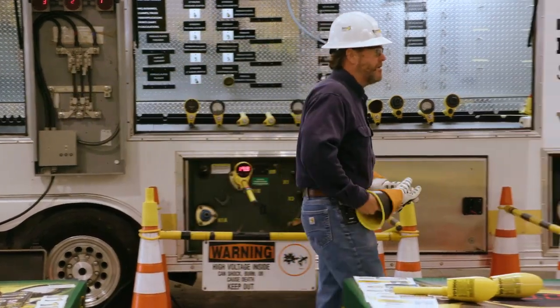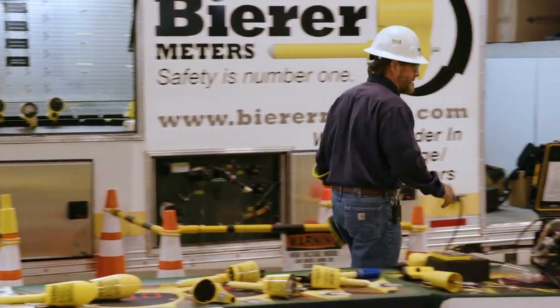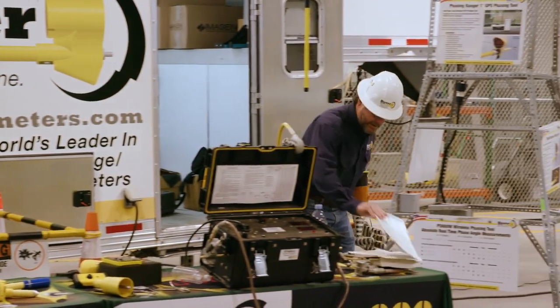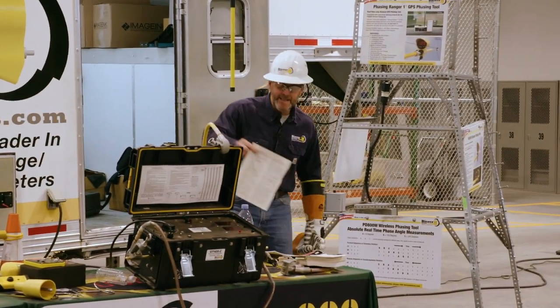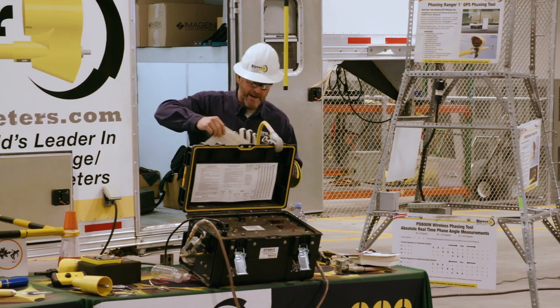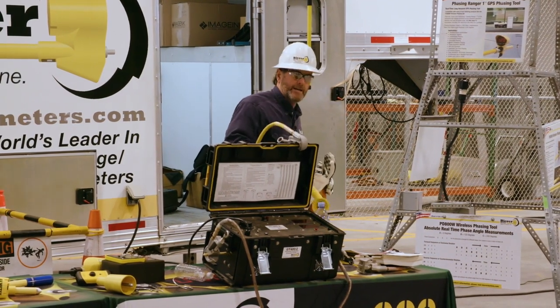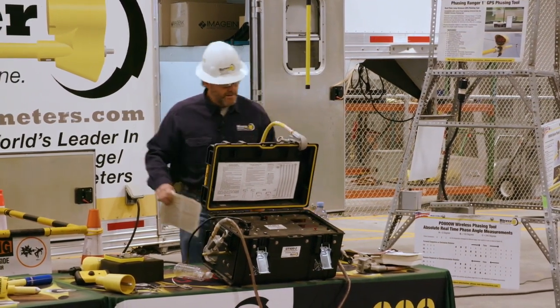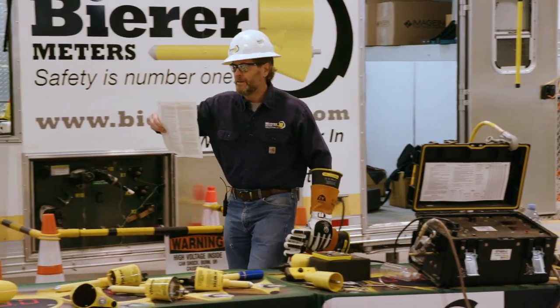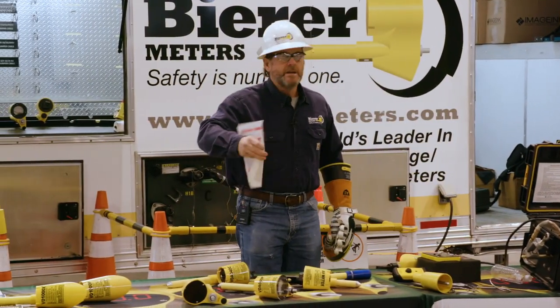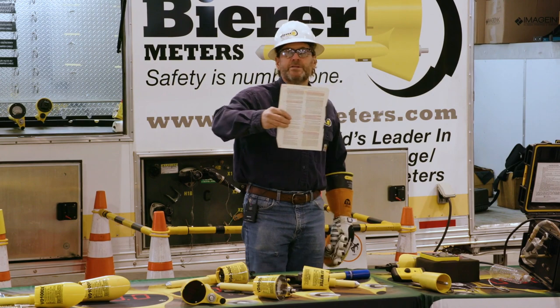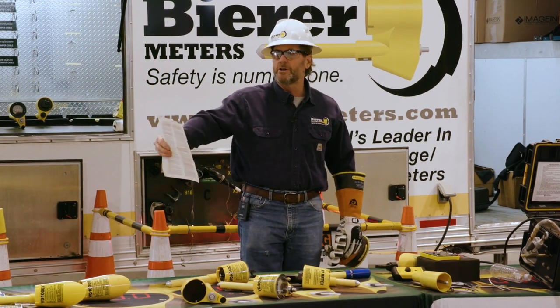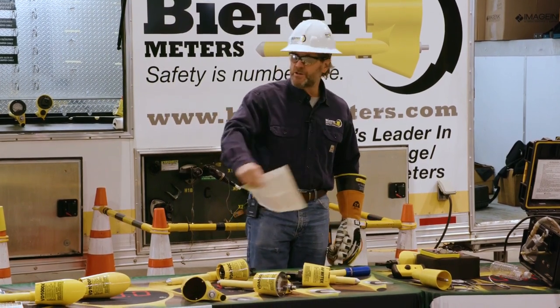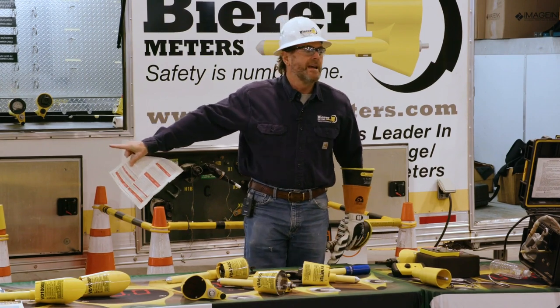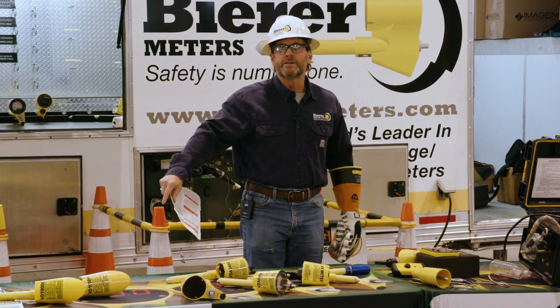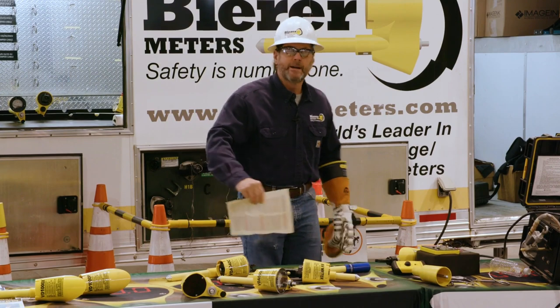So in OSHA 1910.269, go to lowercase n, talking about your temporary protective grounds - right here, elbow ground, cluster ground, whatever. When it talks about your grounds, go to number 5, and it tells you that before you install your TPGs, you're going to use your tester and verify an absence of nominal voltage, correct? Right? Absence.